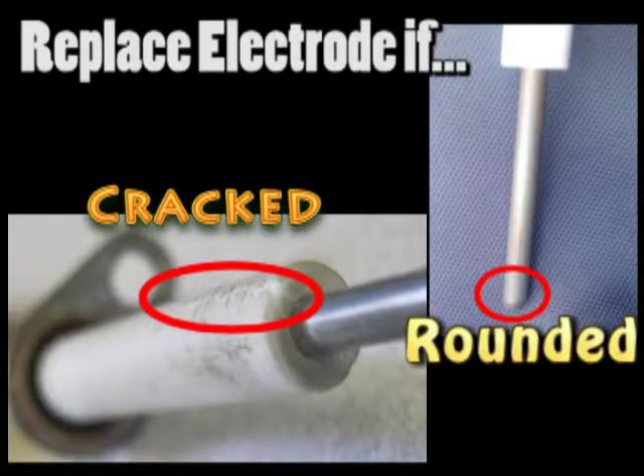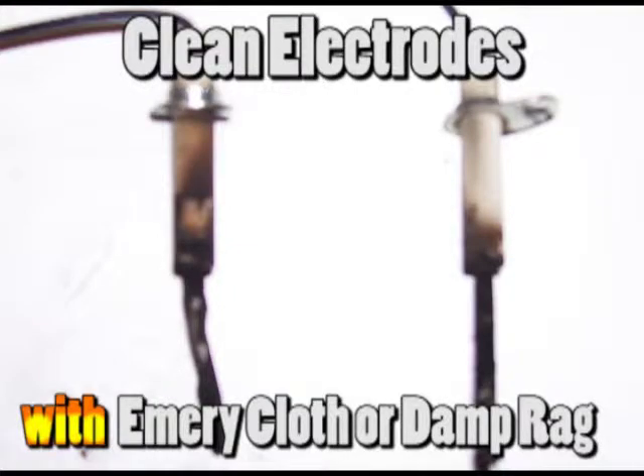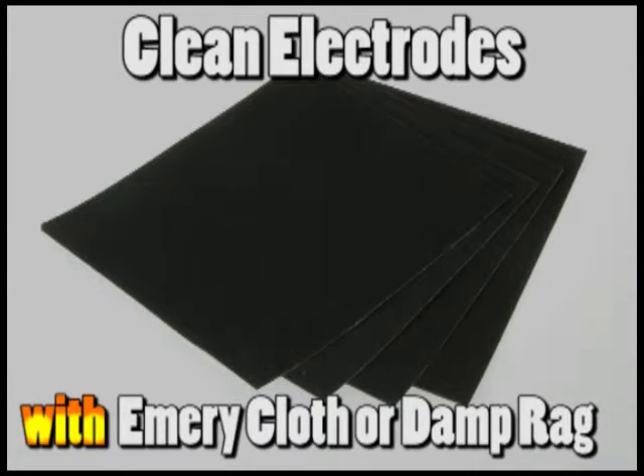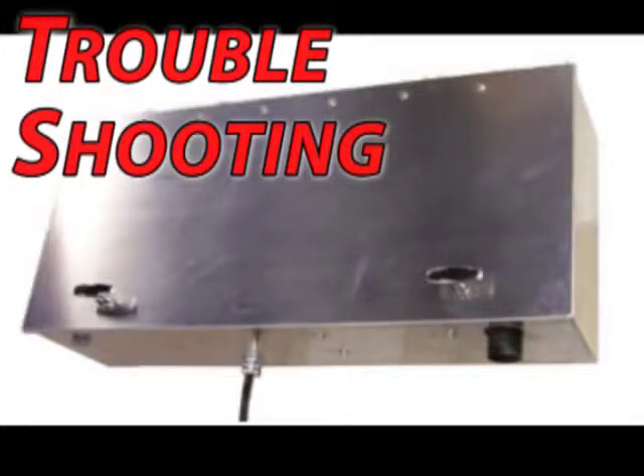If the spark electrode is damaged or excessively round, it needs to be replaced. If deposits are found, carefully remove them with a damp rag or an abrasive pad, such as an emery cloth or a fine grit sandpaper. We will now focus on troubleshooting for the HLC heaters. This section will identify commonly occurring issues and describe potential fixes.